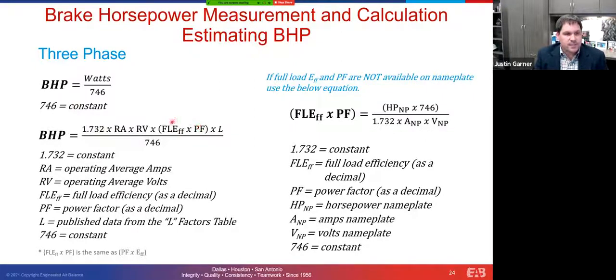And this is essentially dictated by the motor construction itself and the operating point at the time that you're measuring it in the system. I'm going to talk a little bit more about this in detail here in a moment. And then this L is something that's usually forgotten or misunderstood, and we're going to try and dispel those myths today. But this is a load factor. And so this is a factor to derate this right here based upon the motor not being at full load conditions. And I'm going to show you how that plays in as we go through and talk about these calculations.